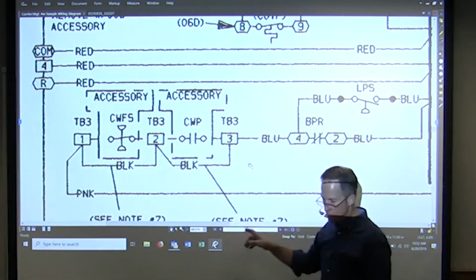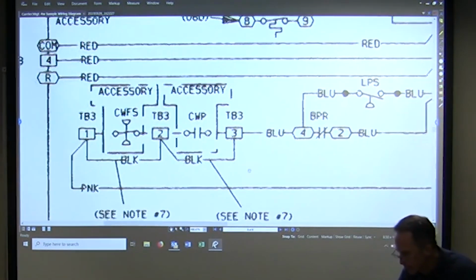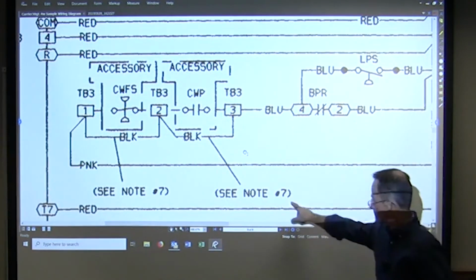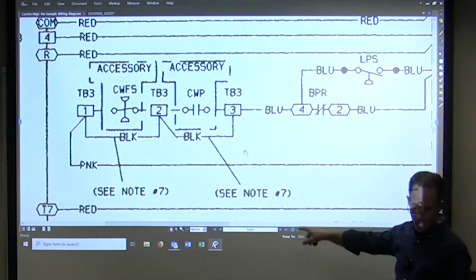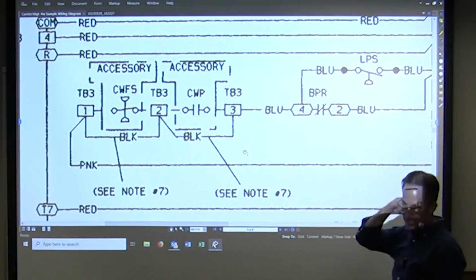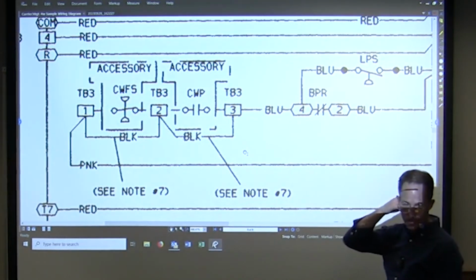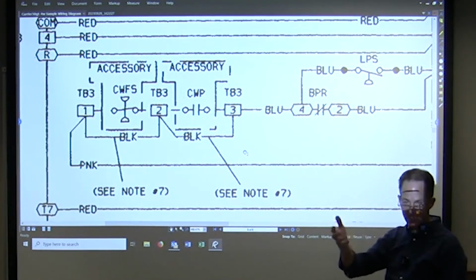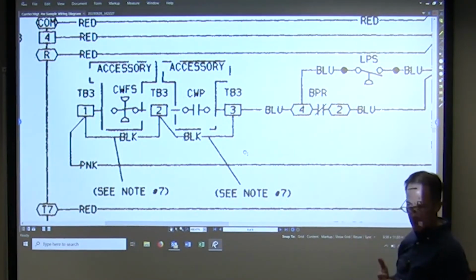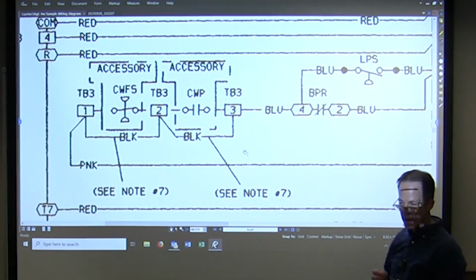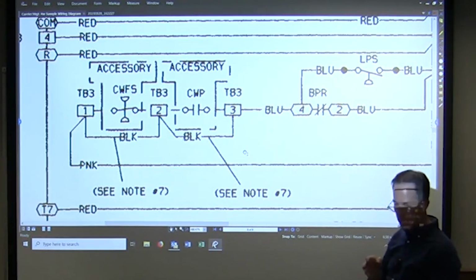But there is a note there. What does the note tell us? Yeah, it even says note 7, it says all field installed. So the note 7 says field installed. What else does it tell us in note 7? Use the right wire. The right wire type has to be able to carry 2 amps, 24 volts. Remove the jumper, the red one. We use red wire. And 1, 2, and 2, and 3. Okay, so what do we need to do? Remove the jumper. So there's a jumper as well that comes, what, from the factory or installed in the field? From the factory.